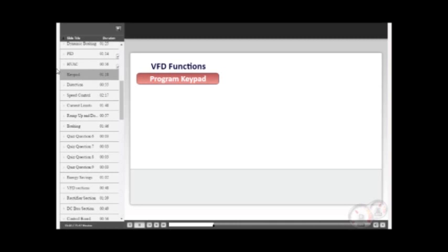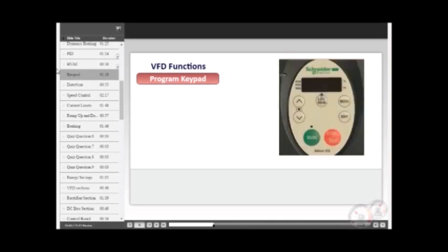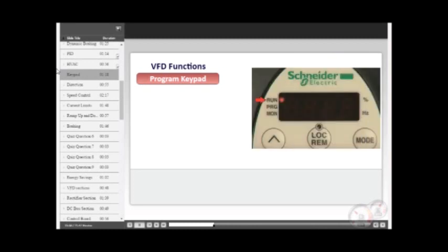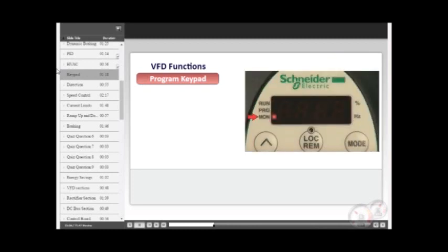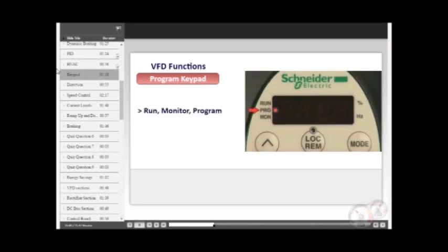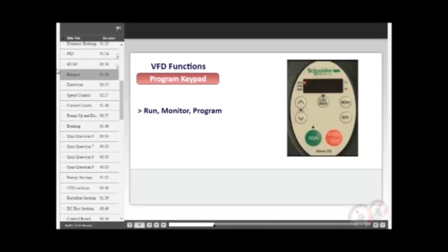Variable frequency drives are set up by using the keypad on the drive. This keypad is also used to run, monitor, and program the drive. Some drives, when first powered up, automatically go into the run mode. They can be easily changed to the monitor mode by toggling the membrane mode switch and again to program by once again pressing the mode switch.